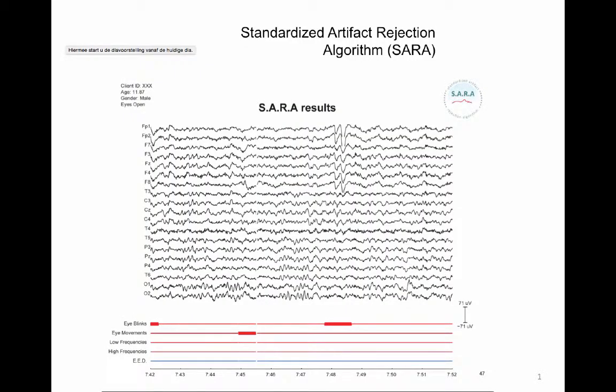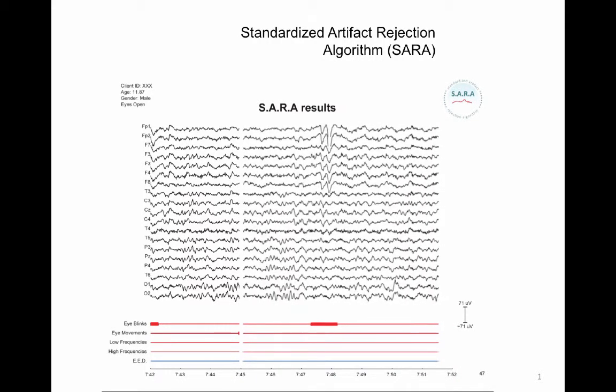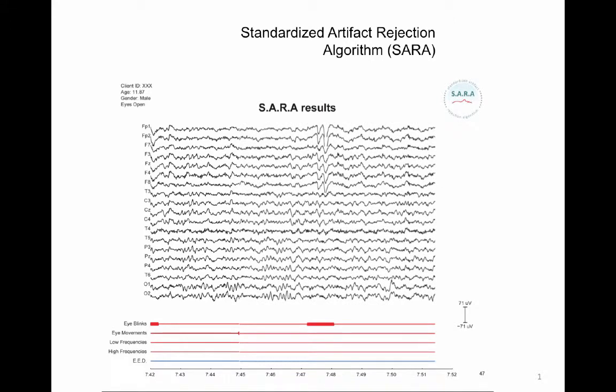SARA has a sophisticated algorithm to prevent the generation of artifacts as a result of removing segments of EEG data. These artifacts are also known as splicing artifacts. SARA uses an algorithm similar to the zero-crossing method in order to make sure the EEG preceding the artifact and the EEG following the artifact are joined together as seamlessly as possible.